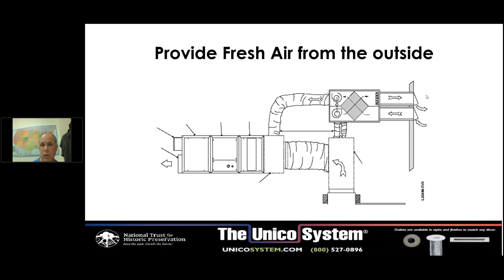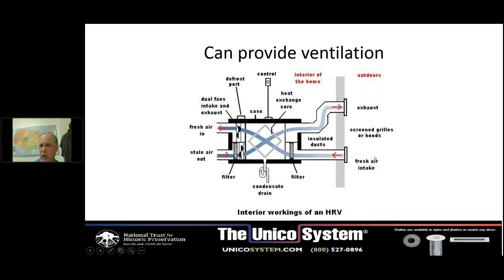Here's more detail: air is generally taken from the kitchen and other wet rooms like the laundry room and bathrooms. The stale air goes out, crossing through the diamond core, while fresh air comes in. These two streams don't mix, but the outside air is warmed by the exchange happening in that diamond, which can be a very light metal or a heavy paper. It's super efficient—you can recover anywhere between 40 and 70% of the exhausted air's heat or coolness to warm or cool the incoming air.